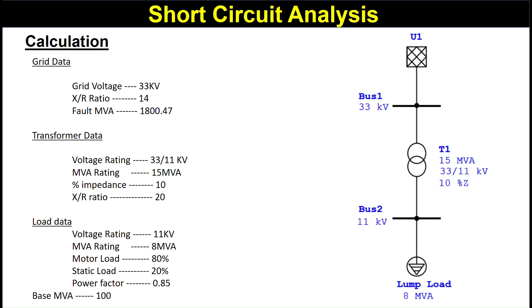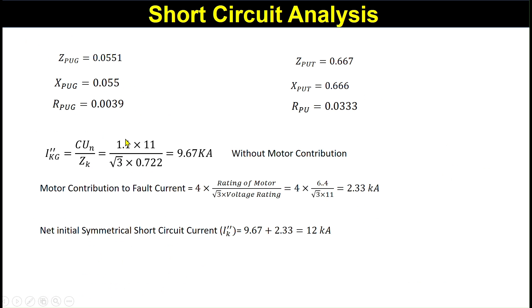In the previous lecture we took this example with the following input data: grid data, transformer data, and load data. We considered a base MVA of 100. Our load is 8 MVA, with 80% motor load and 20% static load at a power factor of 0.85. We calculated the percentage impedance, reactance, and resistance of the grid and transformer on a 100 MVA base, and also calculated the initial symmetrical short circuit current.